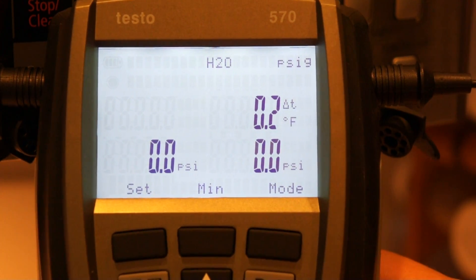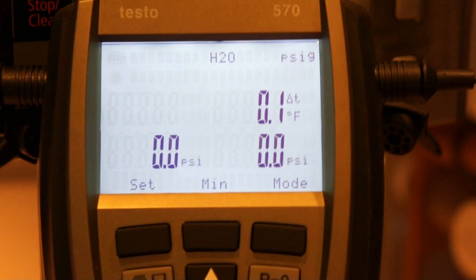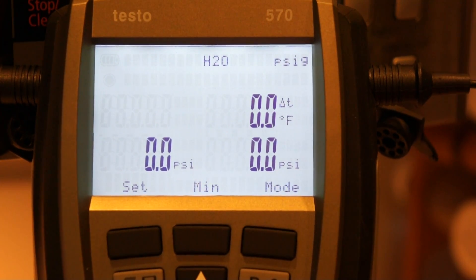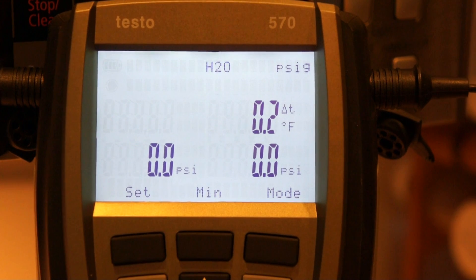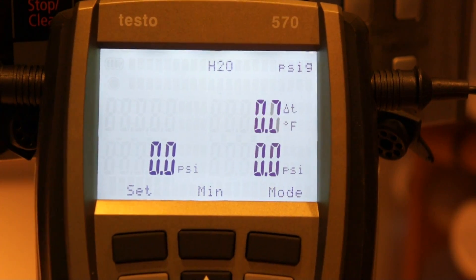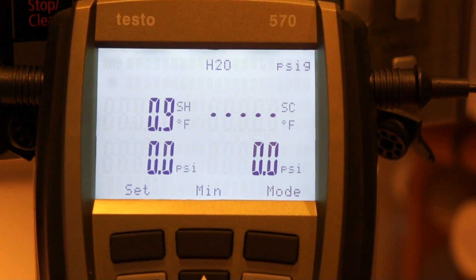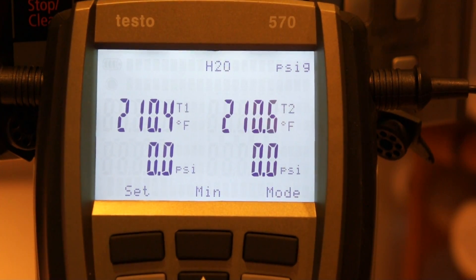You're going to get small changes in the water just because it's moving around and you're going to see that. So that's not anything abnormal. You can see those two temperature probes are running almost right on the money with each other all the time. And again, we have no subcooling and just a small amount of superheat on the display.